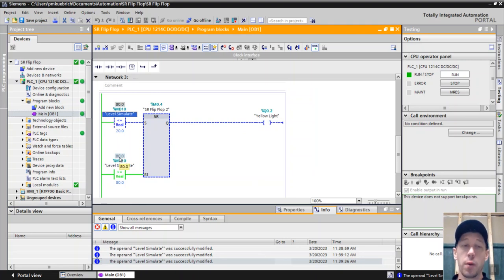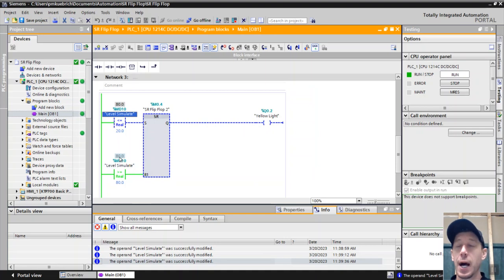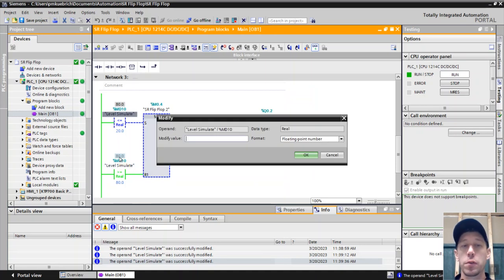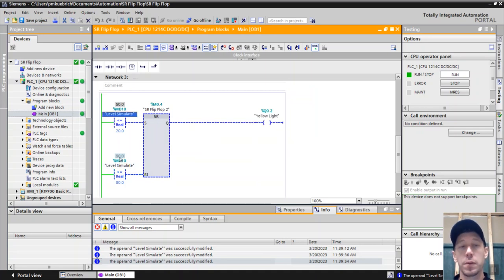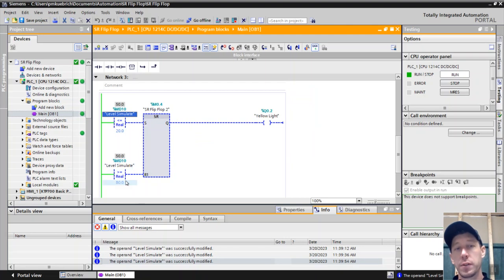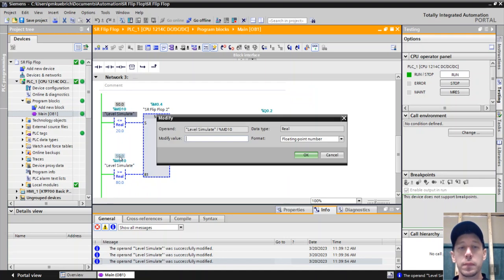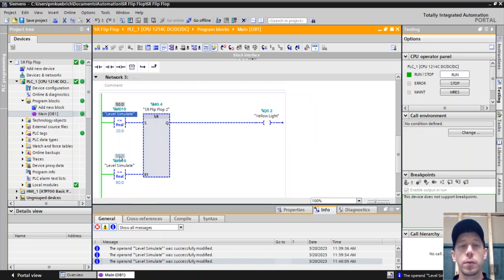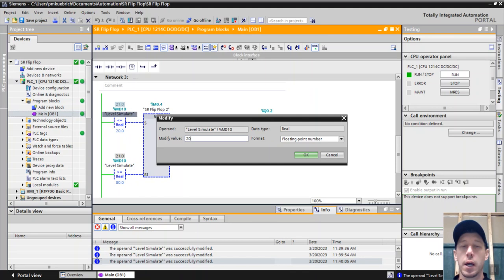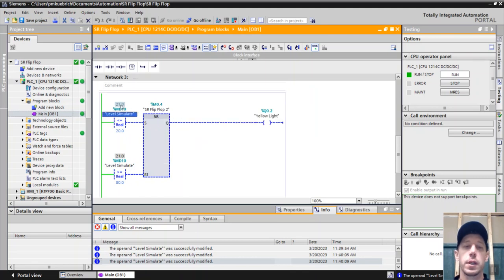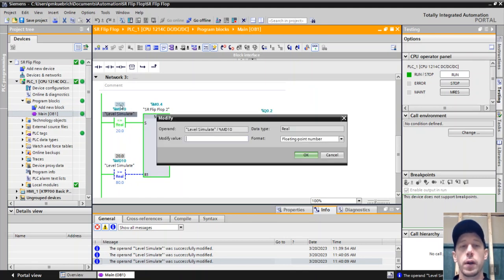Again, this is why we use a set-reset flip-flop and not just a start-stop function, because now what happens when I'm going to go back to fifty percent? Both bits are false. The pump does not restart. Just because we got below eighty, the pump does not restart. Even if I get all the way down to twenty-one percent, the pump will not restart until I am at twenty percent. Then it will restart.